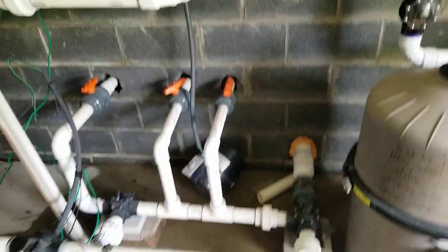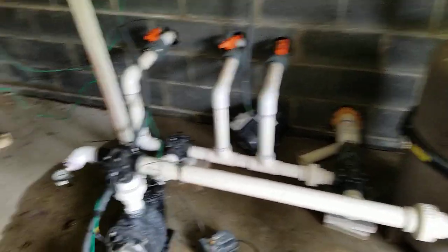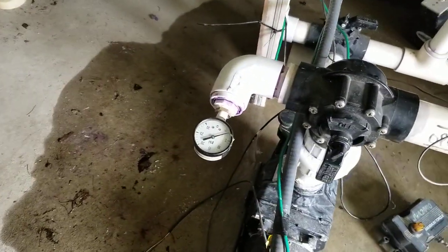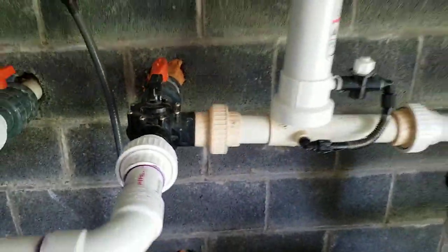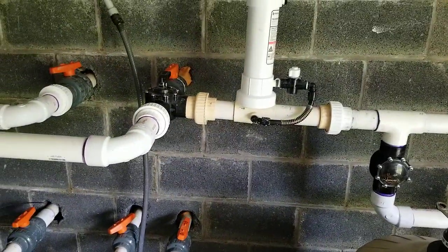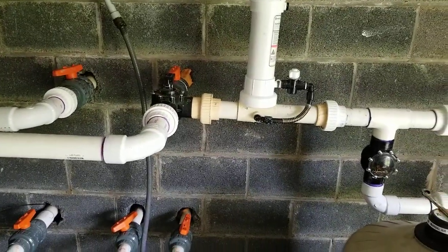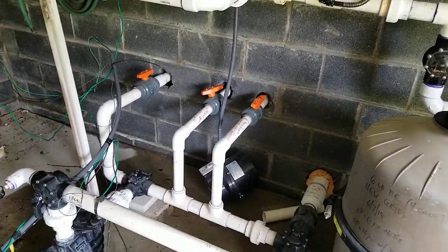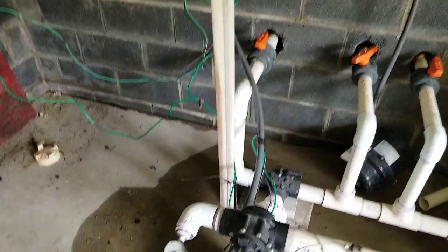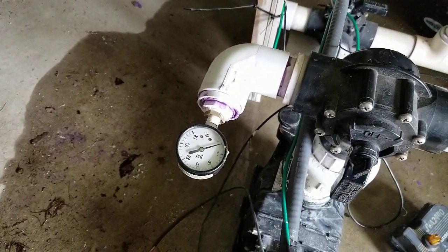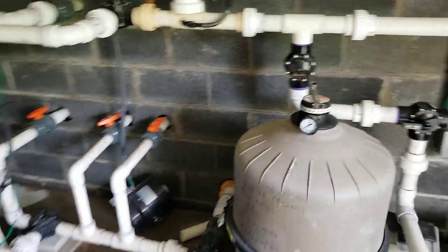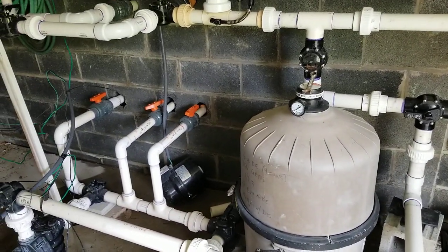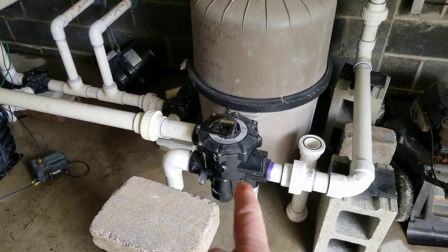So going back to this experiment, we're going to turn on the pump. We're going to measure pressure right here. We're going to have this ball valve wide open and everything else in the system is wide open. So we're maximizing the flow through this leg for this particular experiment, and we're going to get some flow rate at some outlet pressure. We should be able to calculate the expected pressure drop across the entire system for everything except the diverter valve.